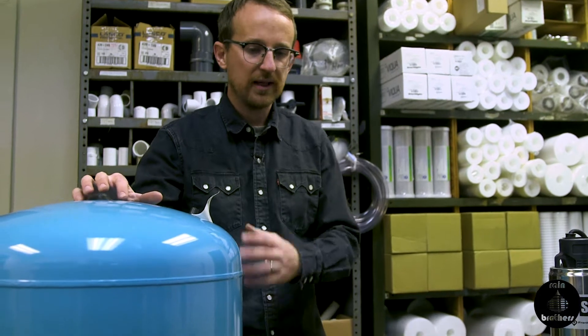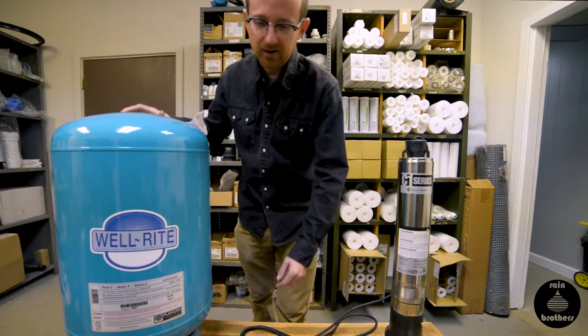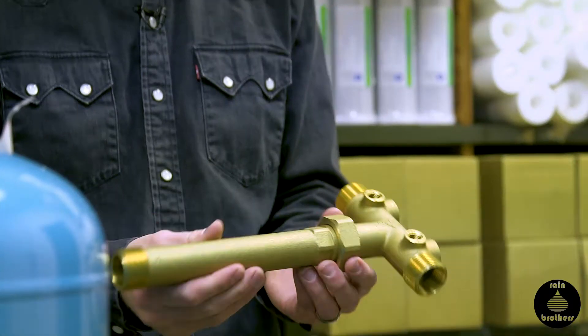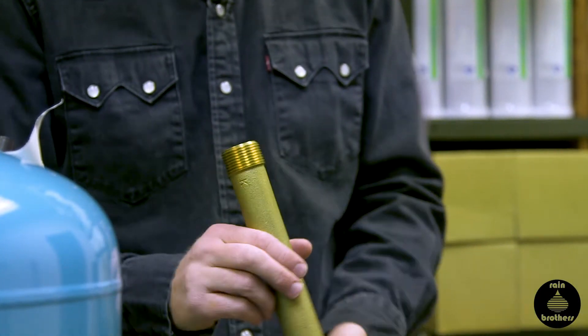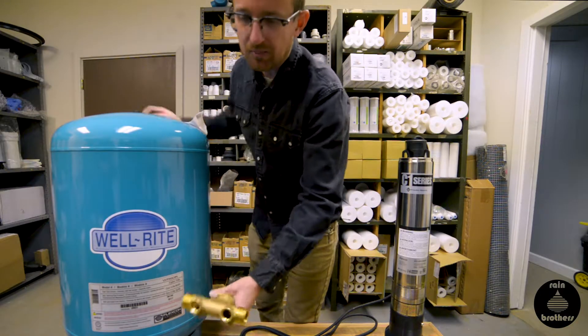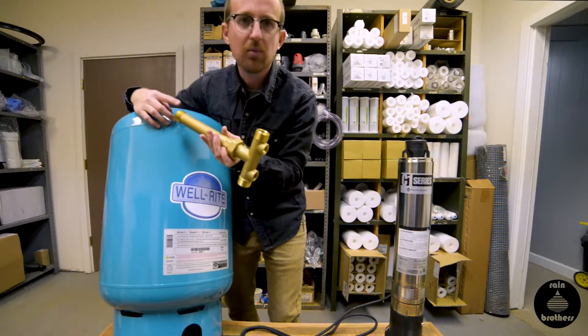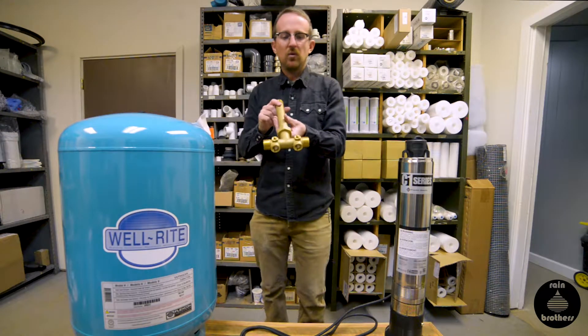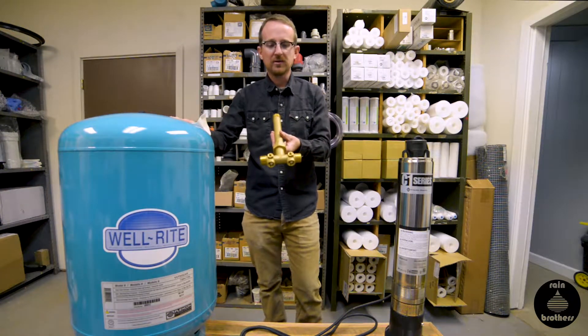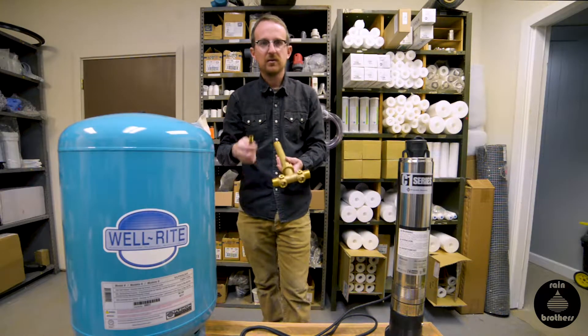This is a Well-Rite 20-gallon pressure tank — our most popular, most common-sized pressure tank. With this particular pressure tank, you'll have a few different components. You have your tank tee, which is a brass tee fitting specifically for pressure tanks. The end of the tank tee threads directly into the bottom of the pressure tank — there is a port there in the bottom this connects to. You'll put Teflon tape or thread seal on the threads, turn it in and tighten it with a pipe wrench. Make sure that when you install the tank tee into the pressure tank, these quarter-inch ports are facing upwards.